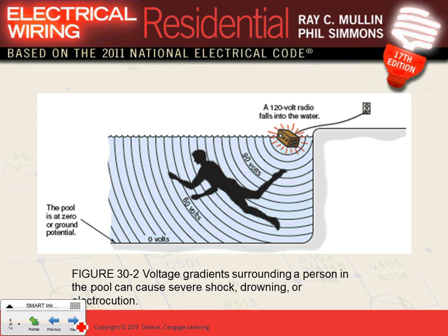So if somebody drops something in the swimming pool, could this happen with a bunch of teenagers drinking and horsing around the swimming pool? Could somebody kick something energized? There were a lot of pictures. There are so many pictures on YouTube where people have a radio like this, a stereo, right in the middle of a swimming pool, floating on plastic bottles. So if this is to trip, you're going to get into something called gradient, guys. So what happens is, if this trips, you're not touching anything. Look what happens. Then you're going to have the current coming in here, going right through you into the ground.